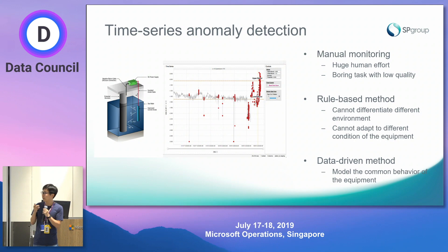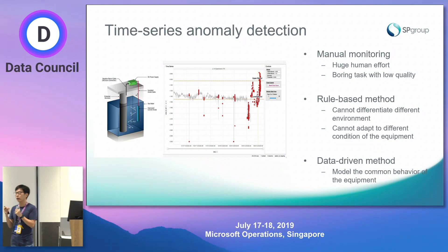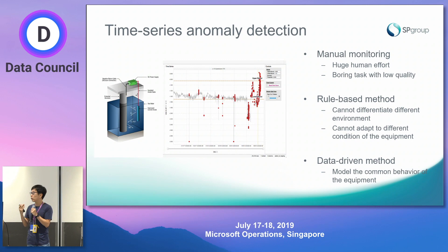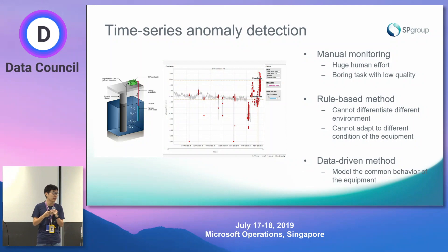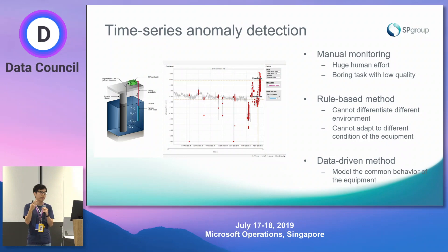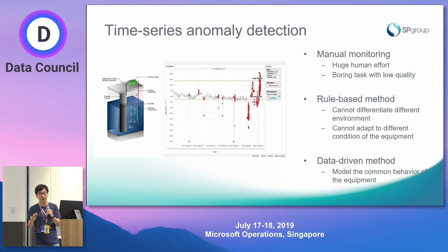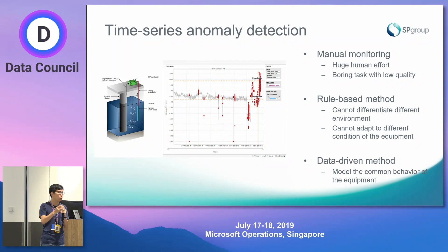The second type is rule-based methods, where you set minimum and maximum values for measurements according to OEM specs — anything within the range is deemed normal, anything outside is deemed abnormal. The disadvantage is that these methods introduce a lot of false alarms, and the fixed setup does not adapt to different environments or situations. The same type of equipment deployed in different environments will behave differently as conditions evolve, so what is normal in one situation may not be normal in another.